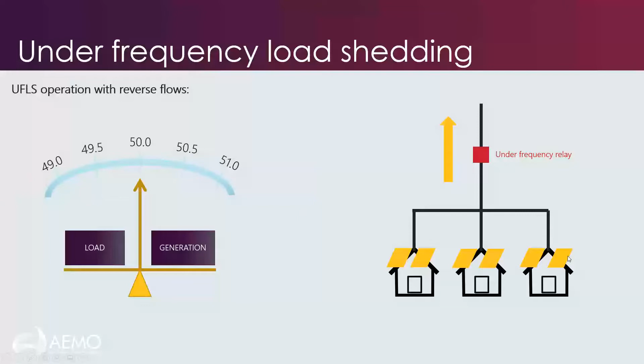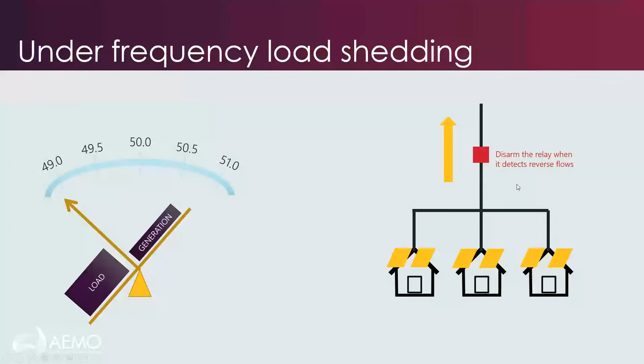Now, we are looking at reverse flow blocking or dynamic arming of relays, which will mean that the relay will be detecting if the circuit is in reverse flows and it will disarm that circuit, which doesn't bring back the original functionality of the UFLS, but it will at least stop it from operating in reverse and exacerbating the frequency decline. So we're now very actively looking at this in South Australia with SA Power Networks, and hopefully we'll get that implemented soon. So to summarise, there's a number of challenges with our under-frequency load shedding.